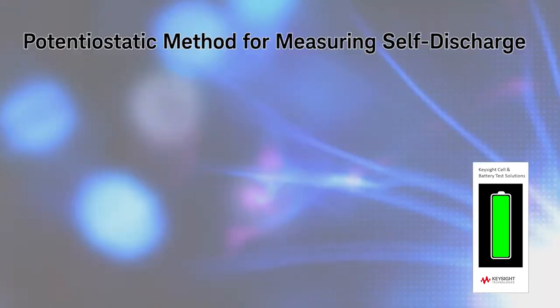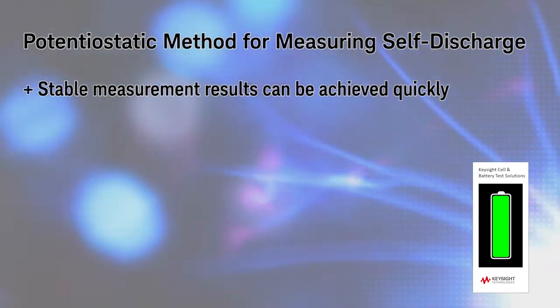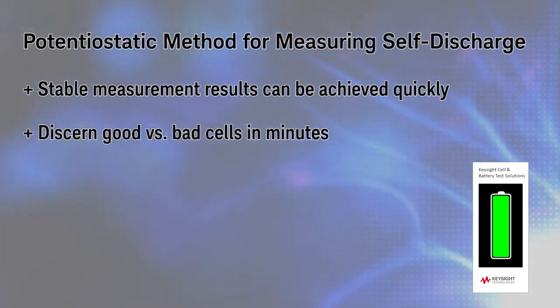The primary advantage of the potentiostatic method of measuring self-discharge is that when executed properly, you can obtain a stable measurement of the self-discharge current very quickly, and you can discern good versus bad cells even faster.